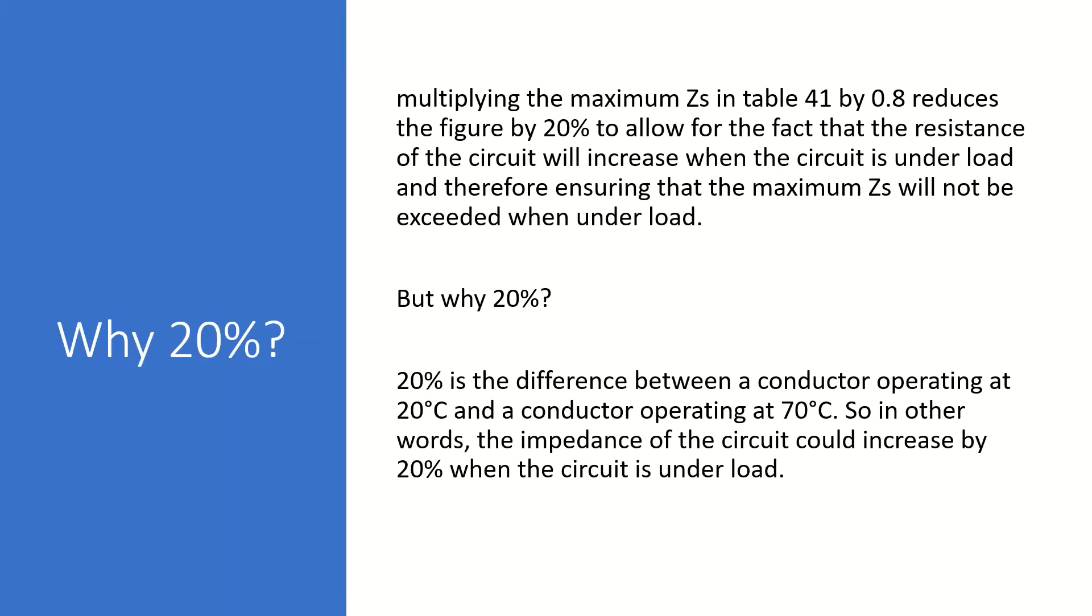So multiplying the maximum Zs in table 41 by 0.8 reduces the figure by 20% to allow for the fact that the resistance of the circuit will increase when the circuit is under load, and therefore ensuring that the maximum Zs will not be exceeded when the circuit is under load.